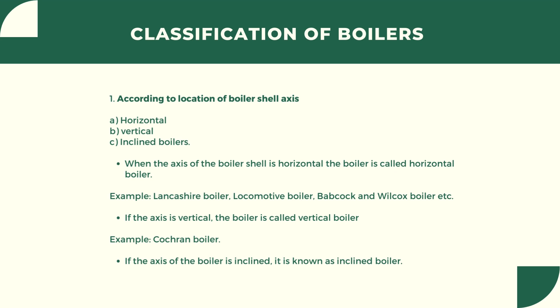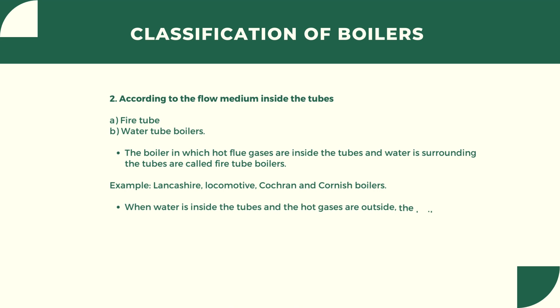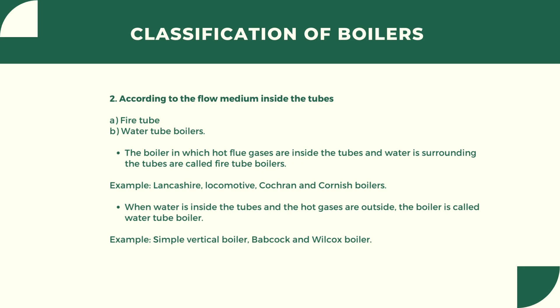According to the flow medium inside the tube, boilers can be classified into two categories: fire tube boiler and water tube boiler. In a fire tube boiler, hot gases are inside the tube and water is surrounding the tube. Examples: Lancashire boiler, locomotive boiler, Cochran boiler and Cornish boiler. When water is inside the tube and hot gases are outside the tube, then that boiler is called a water tube boiler. Examples: simple vertical boiler, Babcock-Wilcox boiler.